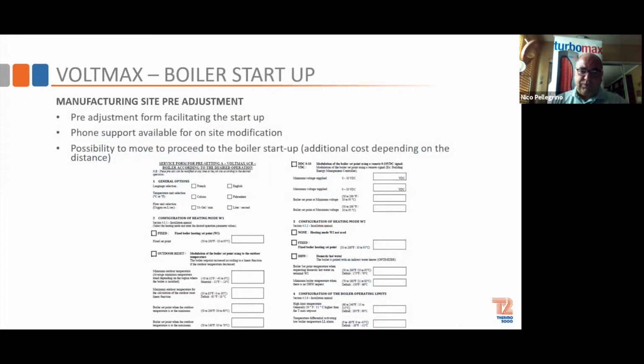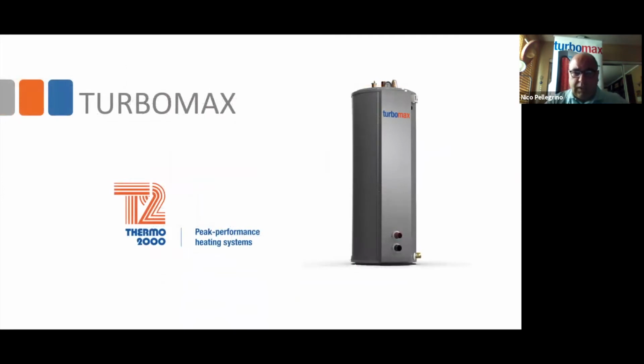So once a PO is sent to us, we have a pre-factory adjustment form that goes out with all our Voltmax boilers. What that does is it allows either the control company or the engineer to tell us what they want this boiler to do, and we actually build it and test it to that. So when it gets out in the field, it's pretty much plug and play. But there's also phone support if you need to do modifications. And if there's internet available, we can get into the program and make changes from the factory. All right, so that's our electric boiler line.